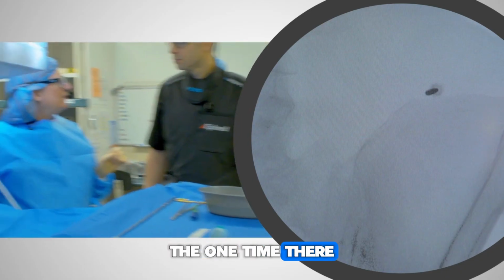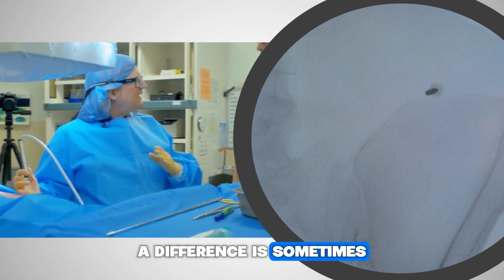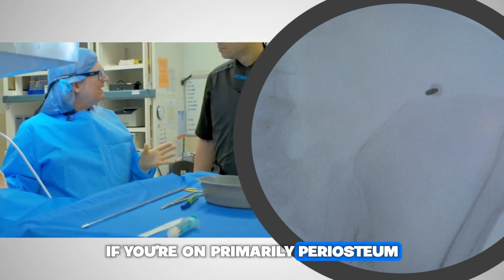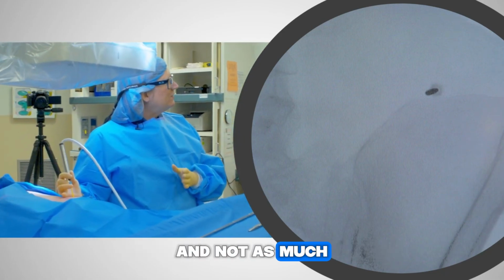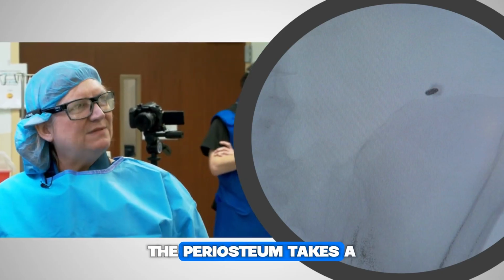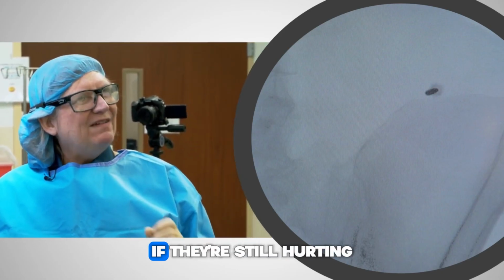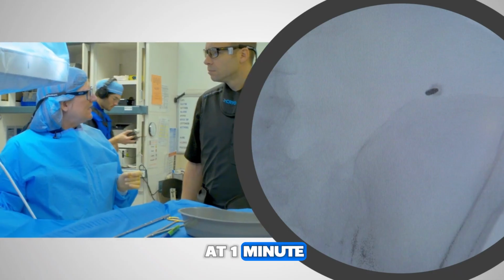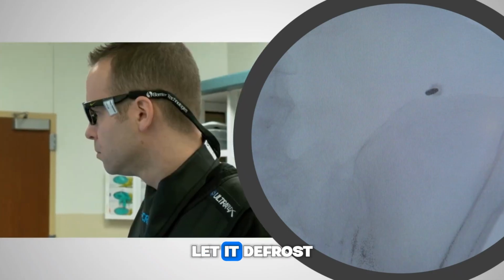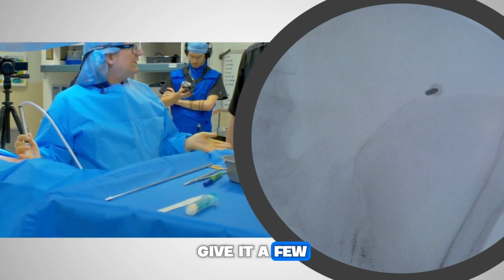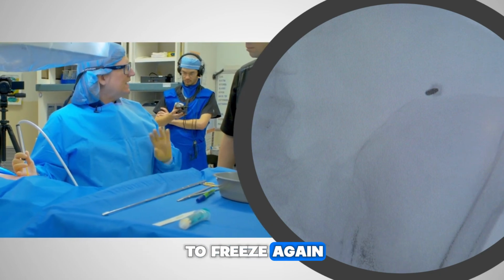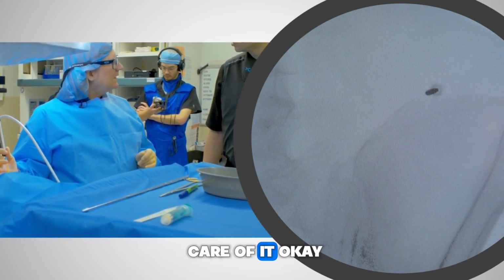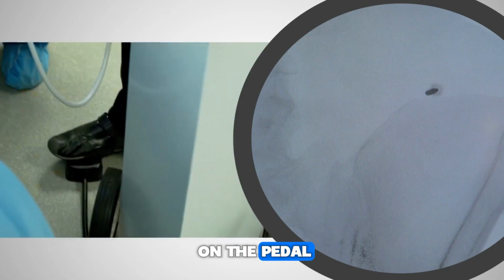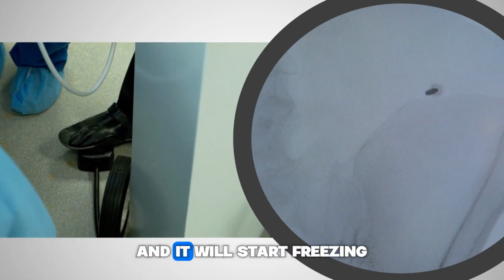The one time there'll be a difference is sometimes if you're on primarily periosteum and not as much the nerve, the periosteum takes a little bit longer to freeze. If they're still hurting at 1 minute, I'll stop, let it defrost, give it a few seconds, and then start to freeze again, and that usually takes care of it. Okay. So go ahead, foot on the pedal, and it will start freezing.